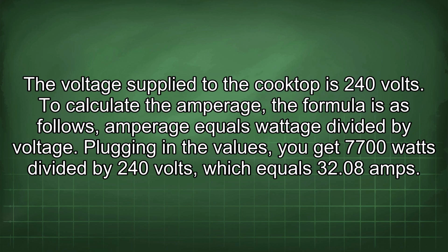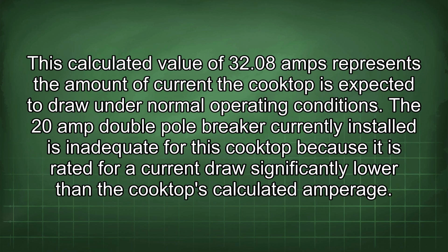To calculate the amperage, the formula is as follows: amperage equals wattage divided by voltage. Plugging in the values, you get 7700 watts divided by 240 volts, which equals 32.08 amps.